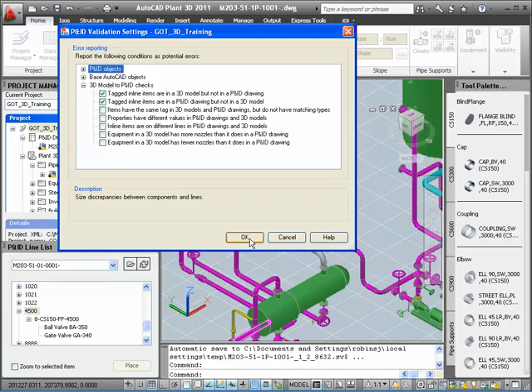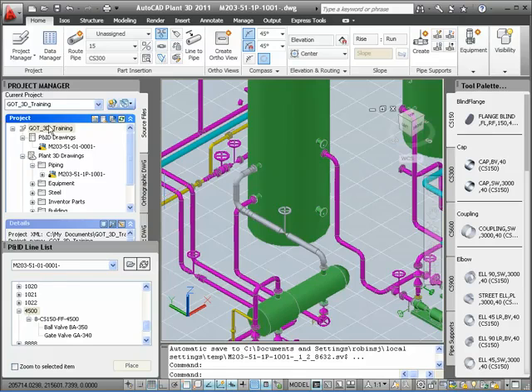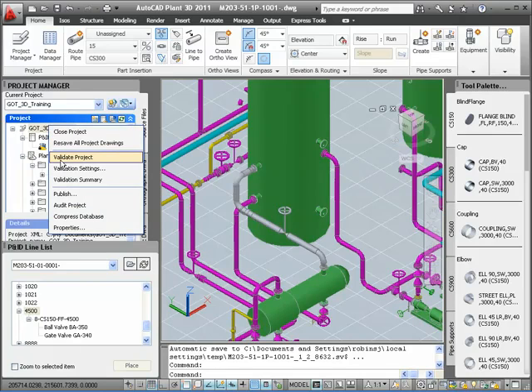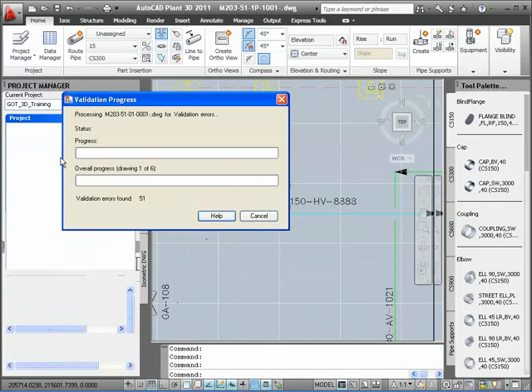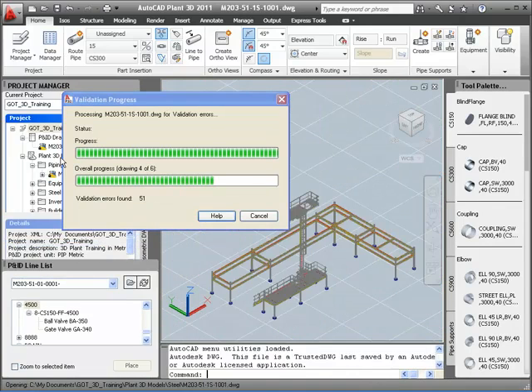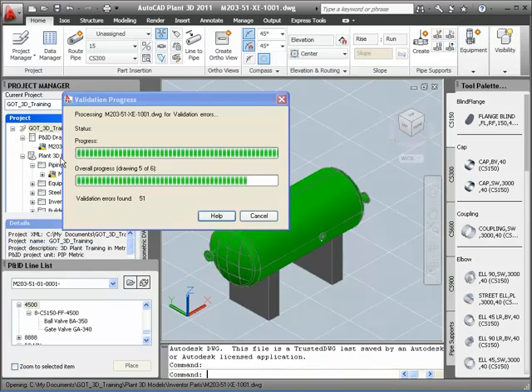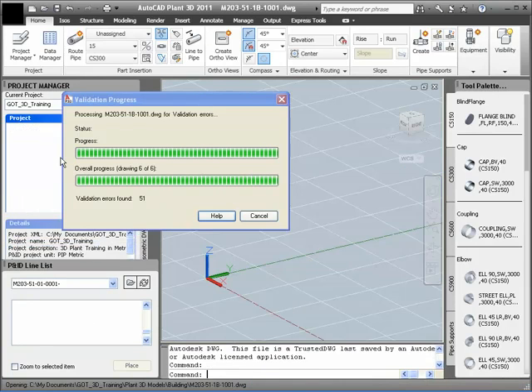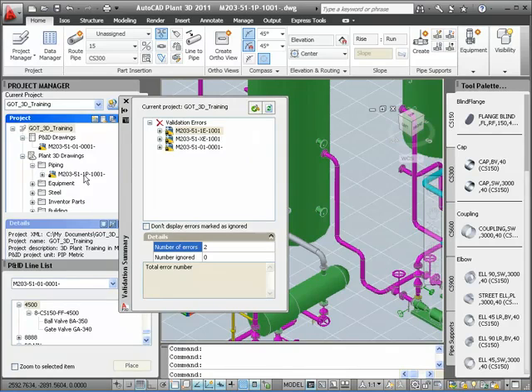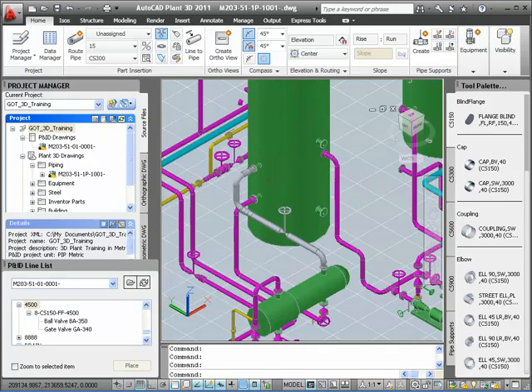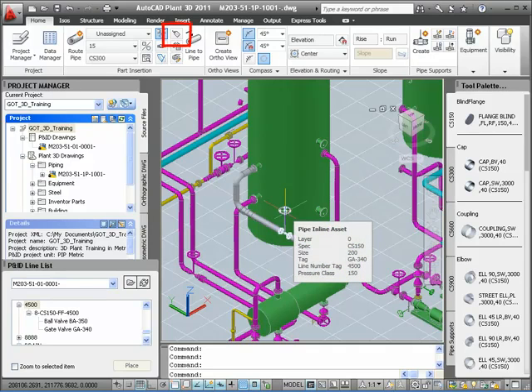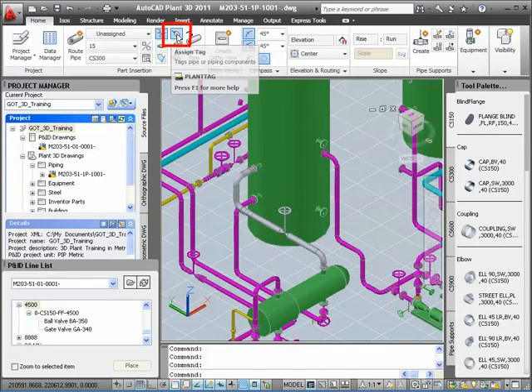I'm going to close the settings dialog and then run the validation process. The program checks each drawing and each reference drawing for any mismatches. The results appear on the validation summary. Depending on the size of your project and your models, this could take some time. You can see here that some drawings did indeed have mismatches, but not our piping drawing, which is not listed. I'm going to change one of the tags in our model and run validation again to show you how the process catches a mismatch. I'll change the tag in the gate valve from GA340 to GA999 and then run the validation again.